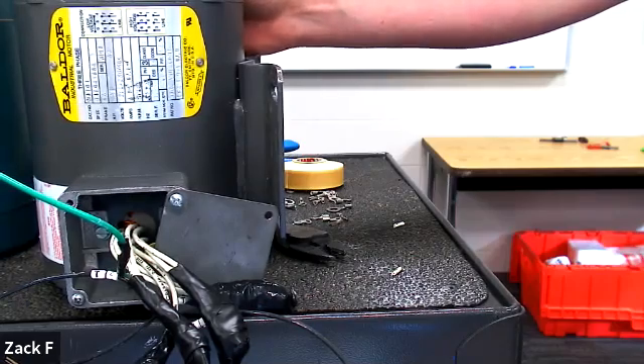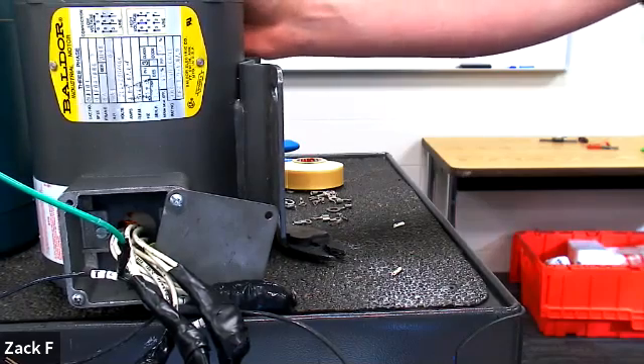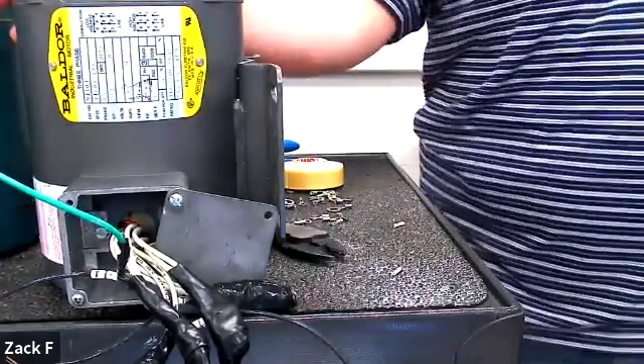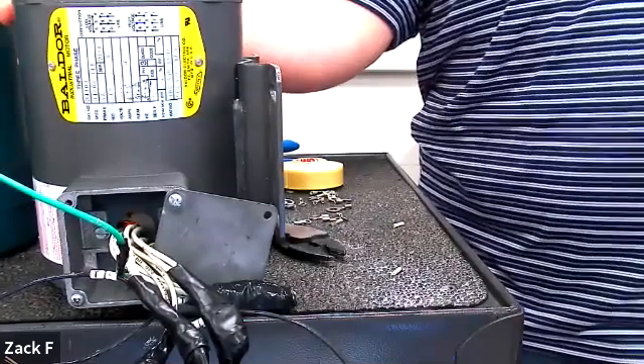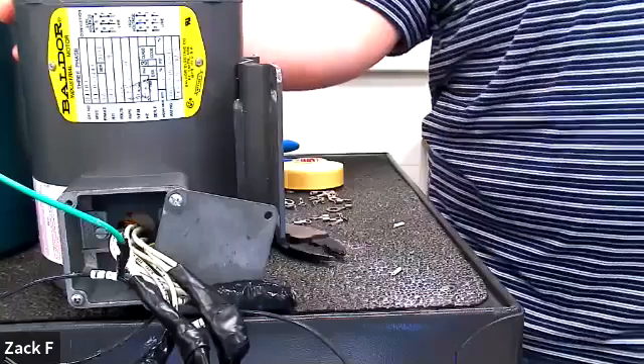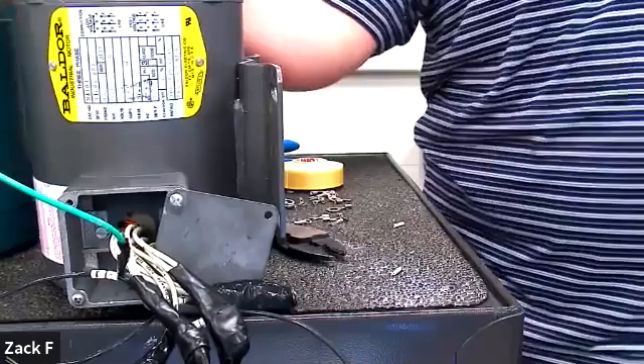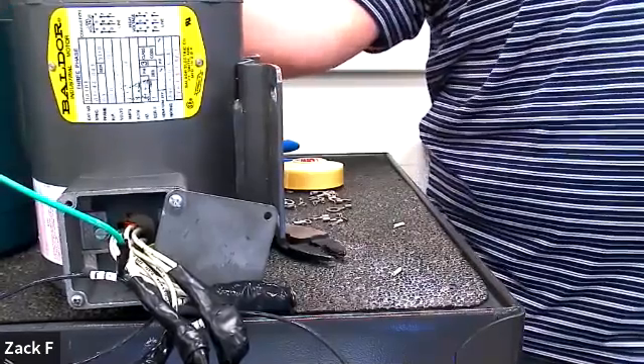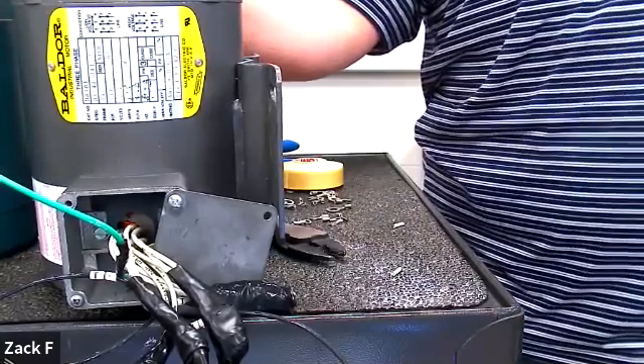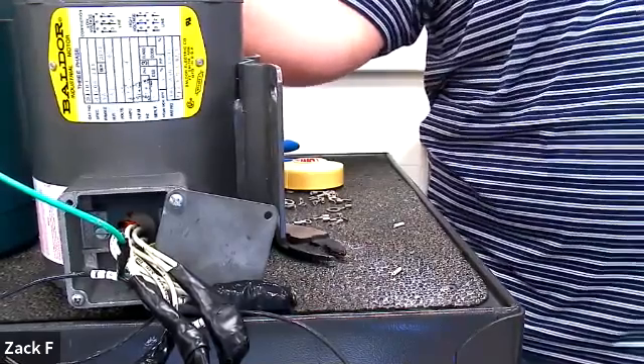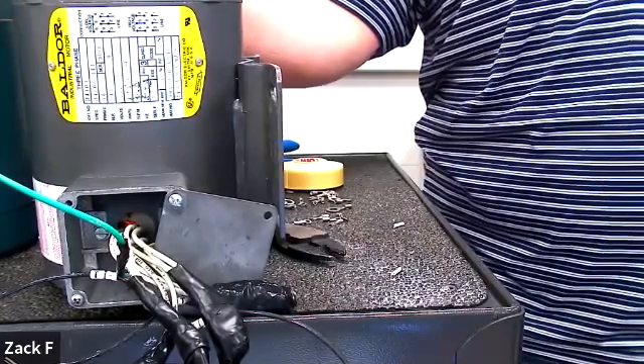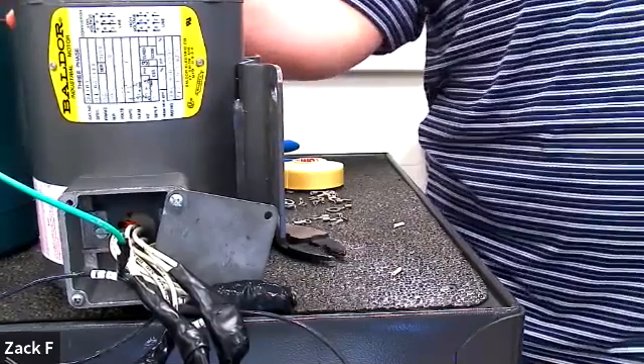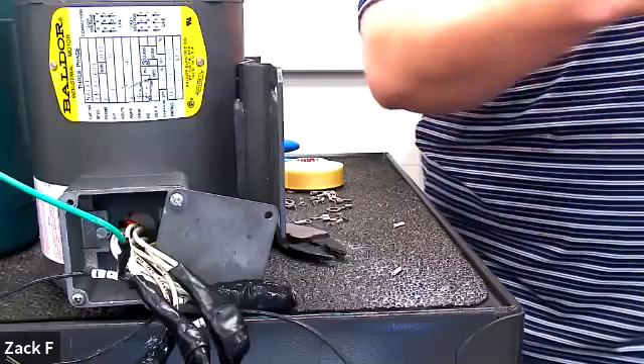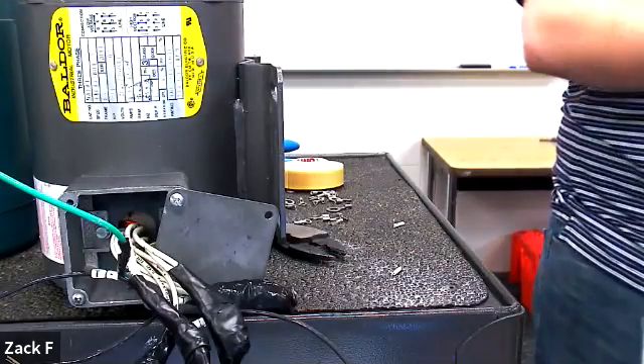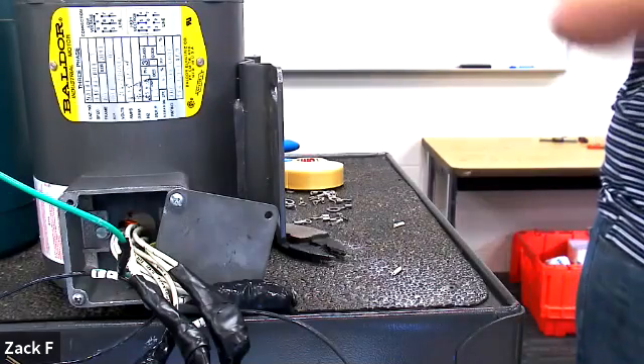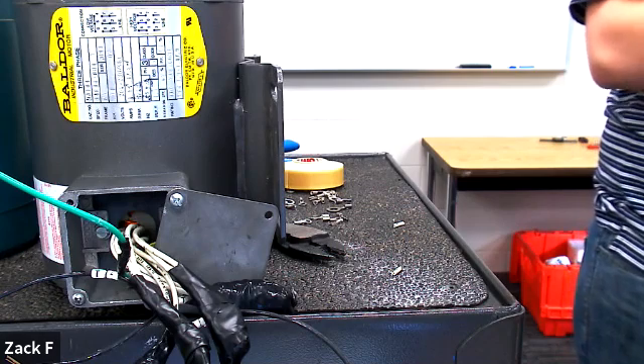I've seen this in the field where you can test something with a meter, have no continuity to ground, have good voltage coming into whatever, a motor, lighting circuit, whatever, and you're still having problems with fuses blowing or whatever. That's because when you put a load on a system, especially a motor, a high load, if there's any pinhole in the insulation, you can get leakage current, and that's what meggers are for. Meggers put out up to, this one goes up to 1,000 volts, and you might not think it puts out that much, well, try it. Don't try it, but you will feel it if you put one of these on each of your fingers.